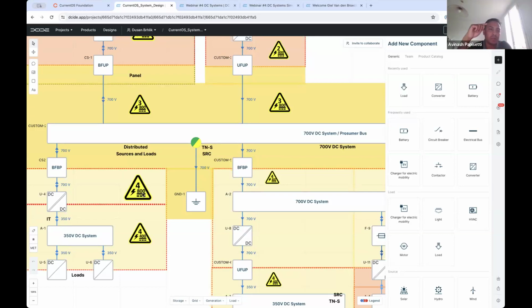It is based on the voltage bands that we have defined in the system specs. We potentially follow 2 voltage levels, like 350 as nominal and 700 as nominal. The upper limit of this voltage, which we call the over voltage band, is tied to a voltage level, and that is what is indicated here. It could also be the voltage level in that area where this zone is put up.